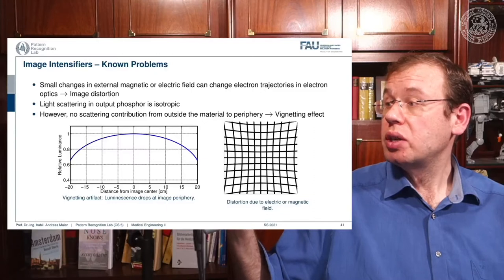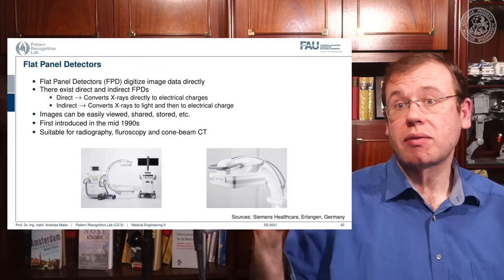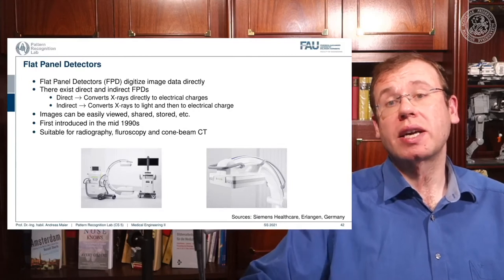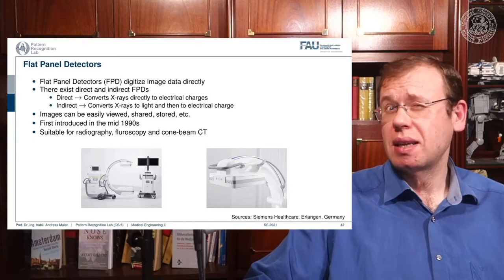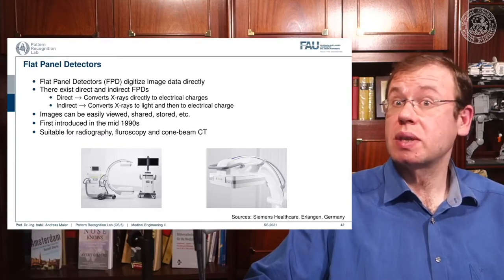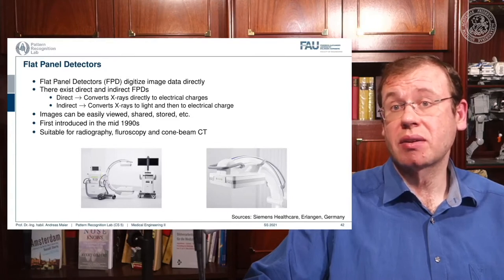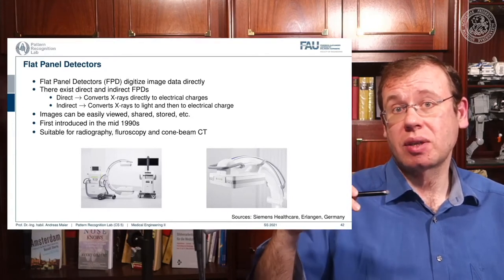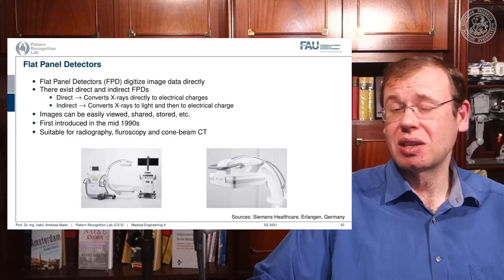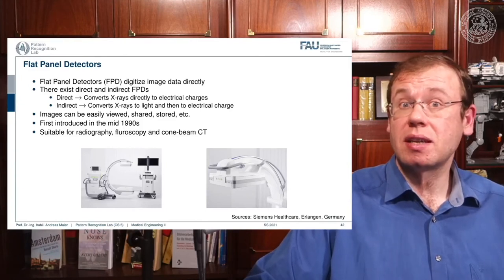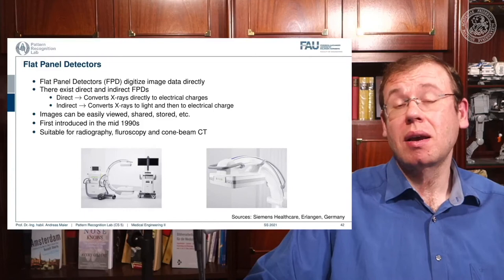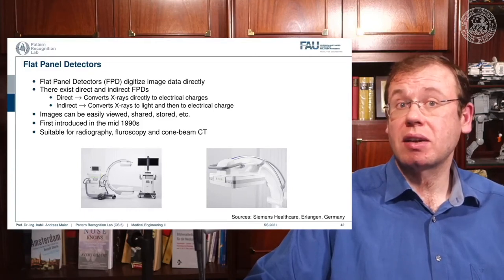An alternative approach is the flat panel detector. Flat panels can also be operated close to a magnetic field, which is very nice. A challenge is operating an x-ray source within a strong magnetic field — a rotating anode inside a strong magnetic field acts essentially like an electronic brake, so it's not clever to use rotating anodes with x-ray sources inside an MR scanner. However, it can be done using a static anode design in that case.